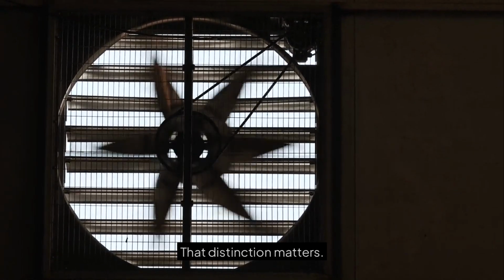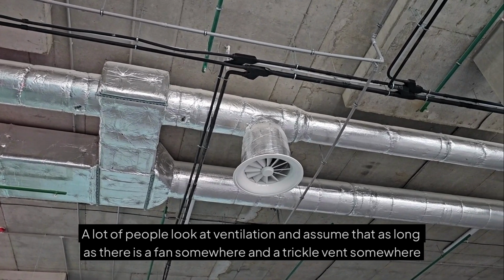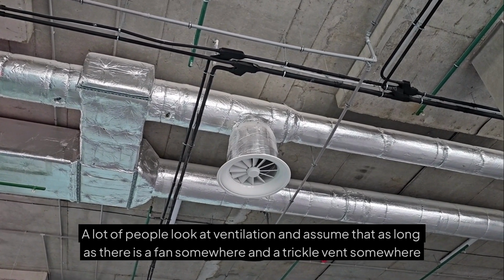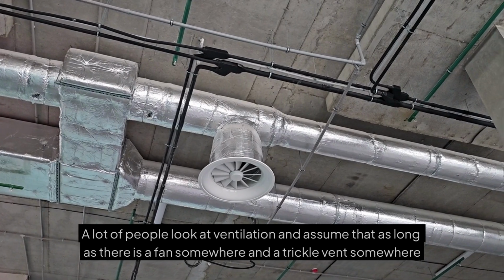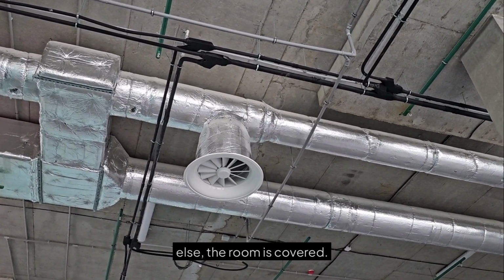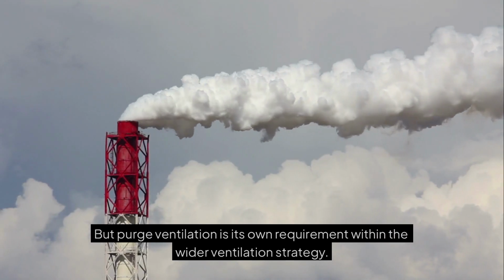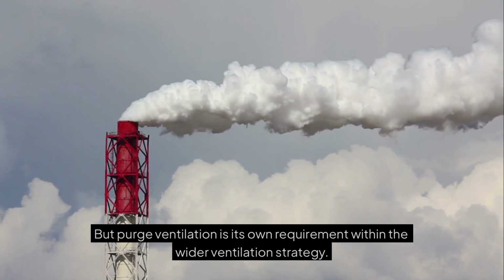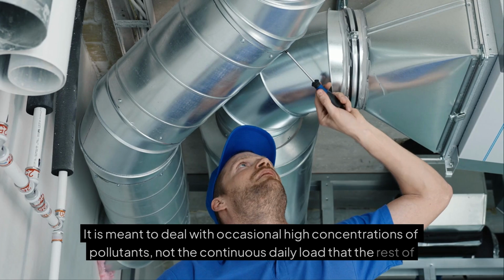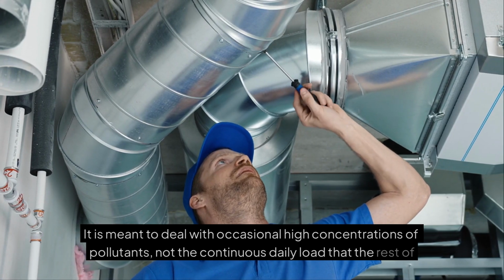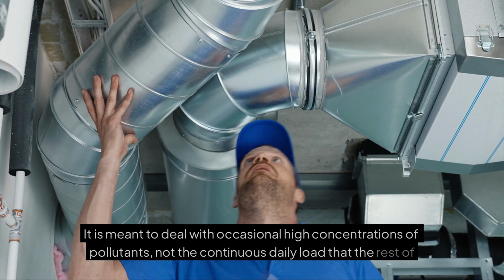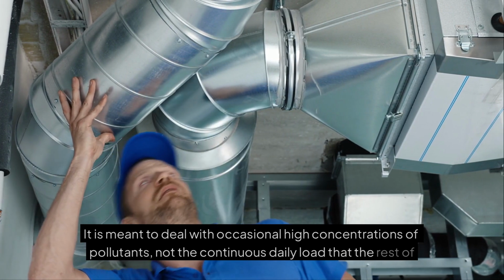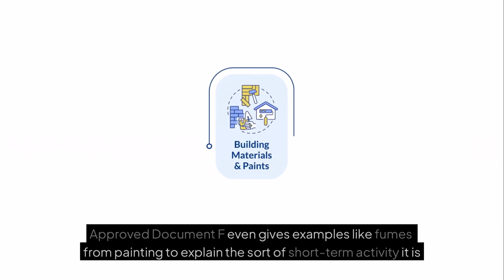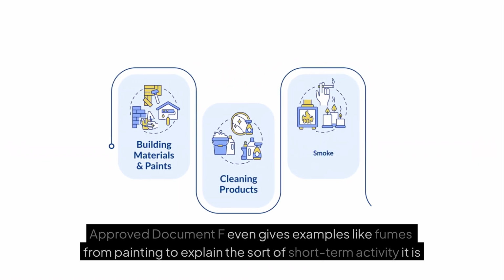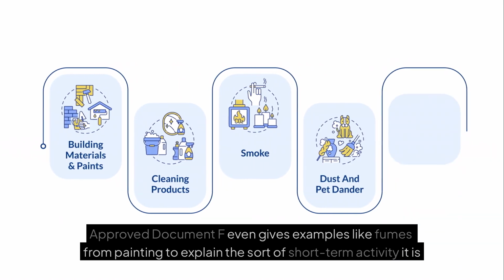That distinction matters. A lot of people look at ventilation and assume that as long as there is a fan somewhere and a trickle vent somewhere else, the room is covered. But purge ventilation is its own requirement within the wider ventilation strategy. It is meant to deal with occasional high concentrations of pollutants, not the continuous daily load that the rest of the system manages. Approved Document F even gives examples like fumes from painting to explain the sort of short-term activity it is intended for.